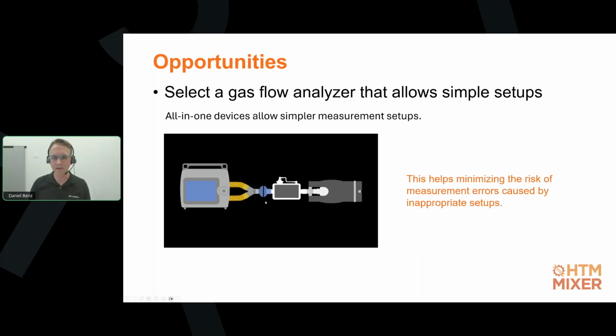You just have to connect the Y piece of the ventilator circuit system on one side of the flow analyzer and the test lung on the other side, and everything else is measured inside the flow channel of the gas flow analyzer. So this helps to reduce the risk of setup-based measurement errors.